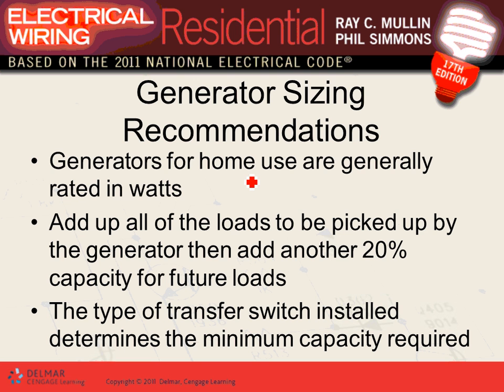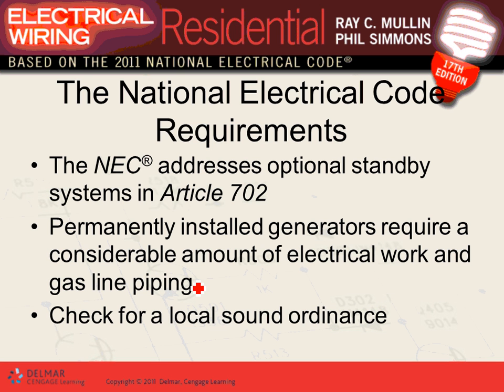Generator sizing. Generator for home. Okay, when you size the generator, guys, typically I will give you software that you're going to be using to size the generator. When you size it for dwellings, you're going to add up all the critical load that you have in the house, and throw 20% extra on it. And then, of course, based on that, you're going to size your transfer switch to be able to handle that. So you size your generator. I have an example here for you. We're going to use it in a second. Like I told you guys, there is an optional standby power system. For dwellings, we go under optional standby systems. That's the article that talks about it. If you go there, it requires you to separate the generator power system from the utility.